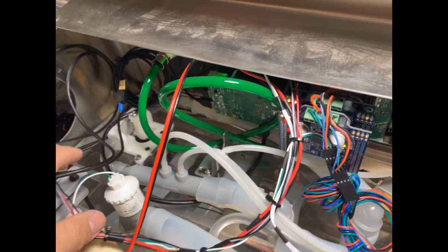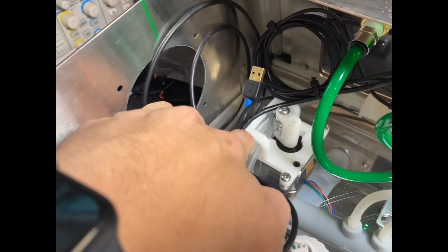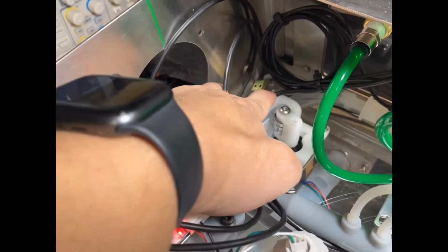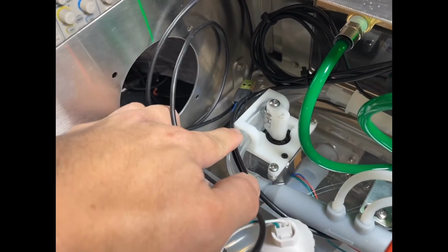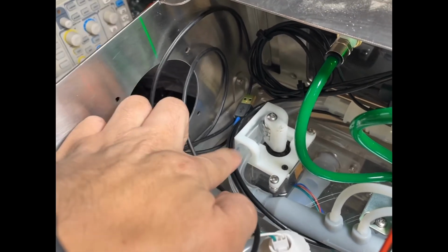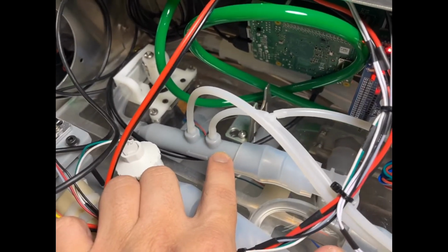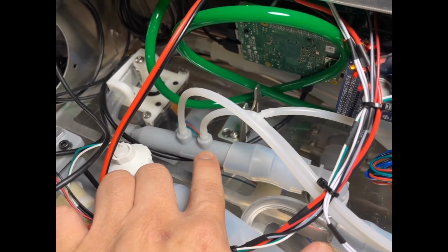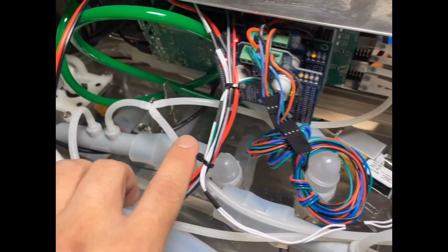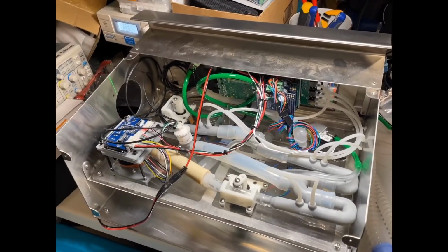Now, when the gas returns from the patient, it comes through this entry here and travels through another one of our stepper motor-based pinch valves. And this allows us to have very good, precise dynamic control of the PEEP pressure, the expiratory pressure. And that comes back through another Venturi, so we measure expiratory flow as well. And this is also where we tap off the patient pressure measurement, and that is how our ventilator works.